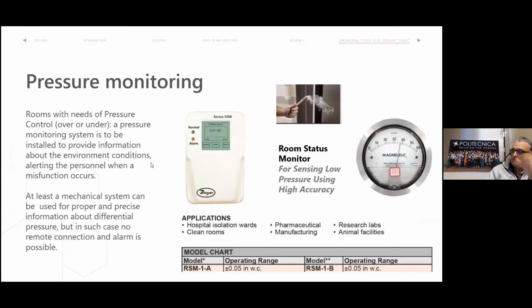As you see here, of course, you have to check the airflow to provide the pressure, but you have to control if the pressure is there. So it is an indicator. It is not a system that is directly connected to the adjustment, but anyway, you must provide an indicator, which is located inside the door, visible from the corridor. It can be an electronic system like this that could be connected to the BMS, could have alarms and whatever, but could be even a purely mechanical system like this, which is Dwyer anyway, the same manufacturer. So this is electronic and this is mechanical.